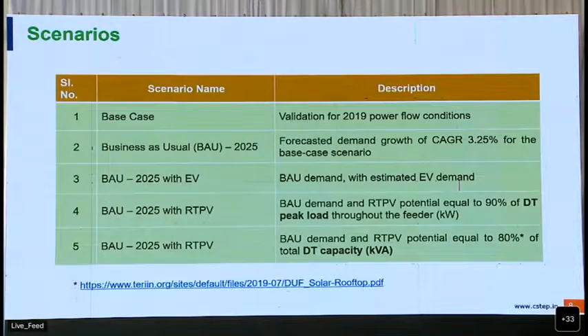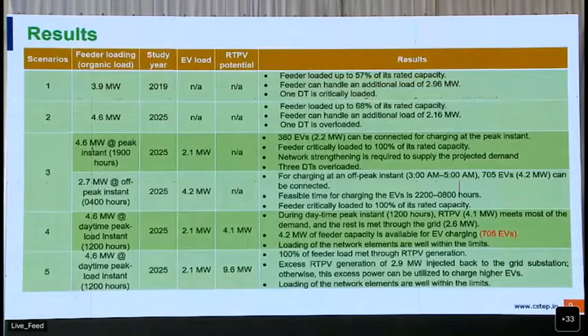The difference between the fourth and fifth is the RTPV potential. In the fourth scenario, the RTPV potential is considered assuming that RTPV can be connected up to 90% of the DT peak load. That means if a particular DT is loaded at 80 kilowatt, then 90% of 80 kilowatt, that means 72 kilowatt of RTPV, can be connected to that DT. But in the fifth scenario, as per the BESCOM guidelines, we have assumed that RTPV can be connected up to 80% of the DT capacity in terms of kVA. So let us see the results from all these scenarios.